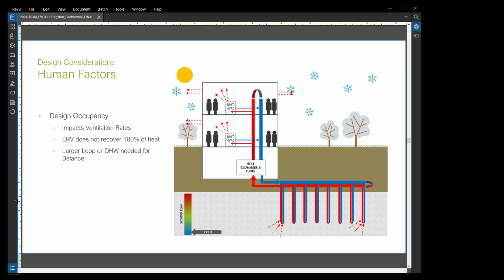The other thing that needs to be considered when you're working through the size of your field and trying to balance things out is what are your occupant loads and what are the assumptions. How do the assumptions that the mechanical designers make compare to what's happening in real life? We've found a lot of conflict on our teams with that, good conflict, challenging each other. The mechanical and electrical teams need to design for absolute maximums, like what is the peak this is going to see, what's the biggest number, can we carry that, throw a factor of safety on it and make sure we've got this nice big number ready to use.